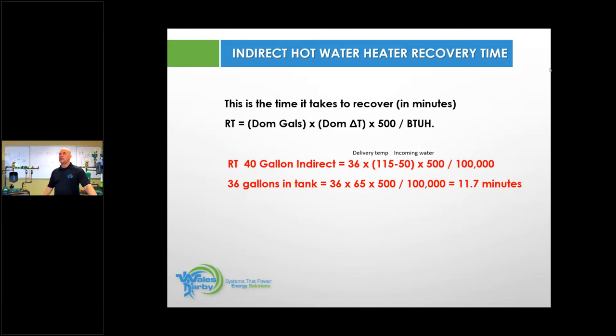You can utilize this in a lot of different scenarios. If it was a direct fired water heater, you could do the same thing, divide it out by, you know, if it's a 40,000 BTU water heater, you would make this 40,000 BTU, and you would come up with your time in the 20 somewhere to make that tank hot again. So very useful. Put this somewhere, you know, in your truck. This is a keeper.